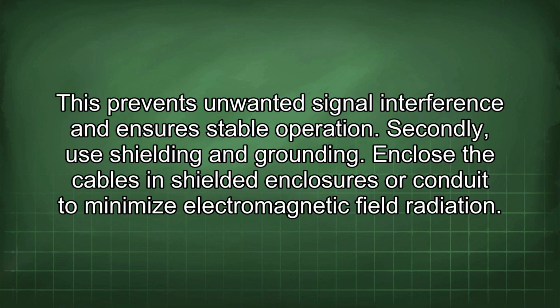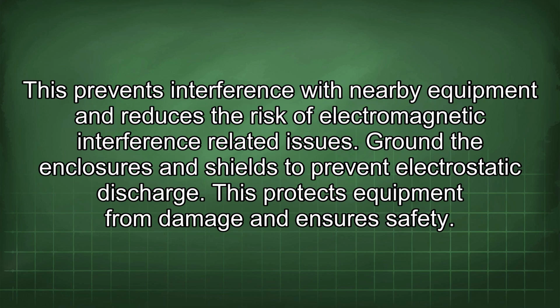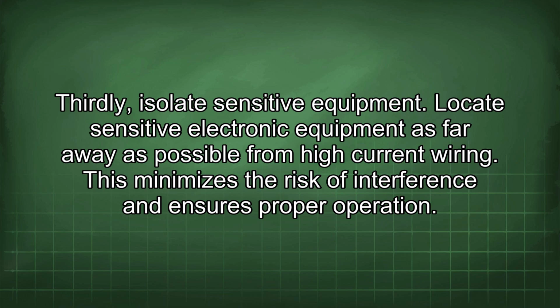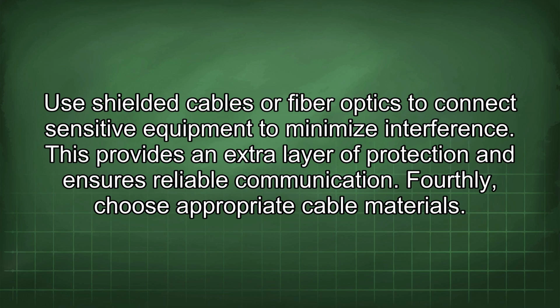Secondly, use shielding and grounding. Enclose the cables in shielded enclosures or conduit to minimize electromagnetic field radiation. This prevents interference with nearby equipment and reduces the risk of electromagnetic interference-related issues. Ground the enclosures and shields to prevent electrostatic discharge. This protects equipment from damage and ensures safety. Thirdly, isolate sensitive equipment. Locate sensitive electronic equipment as far away as possible from high current wiring. This minimizes the risk of interference and ensures proper operation. Use shielded cables or fiber optics to connect sensitive equipment to minimize interference. This provides an extra layer of protection and ensures reliable communication.